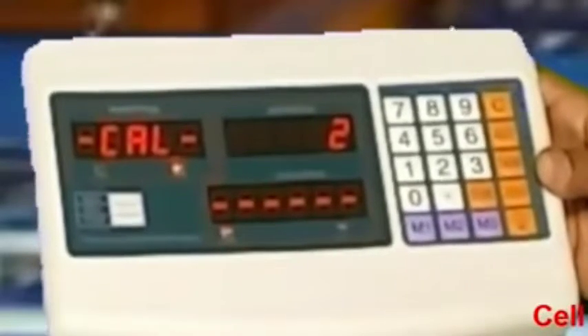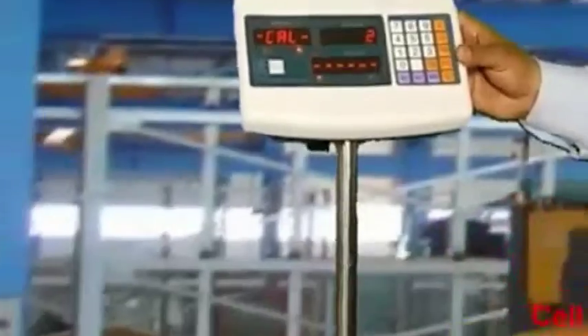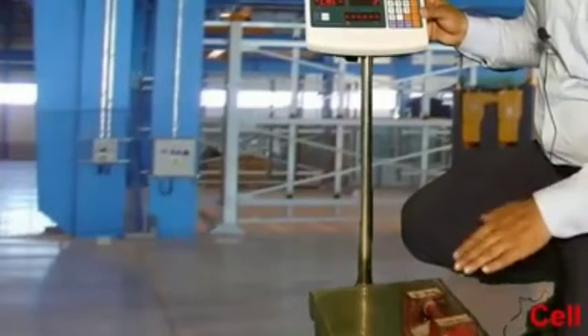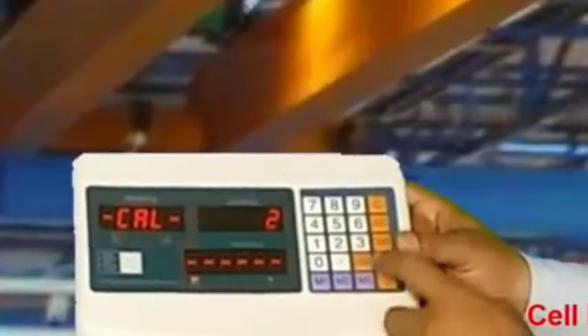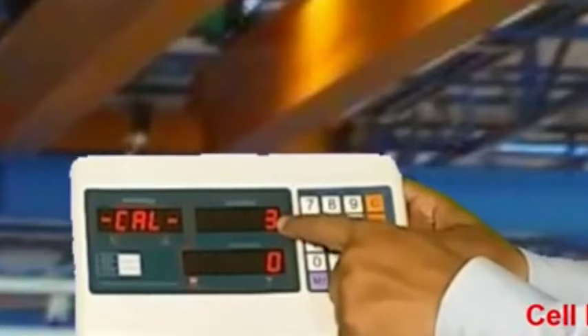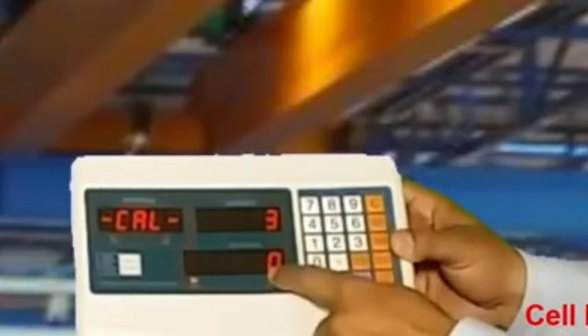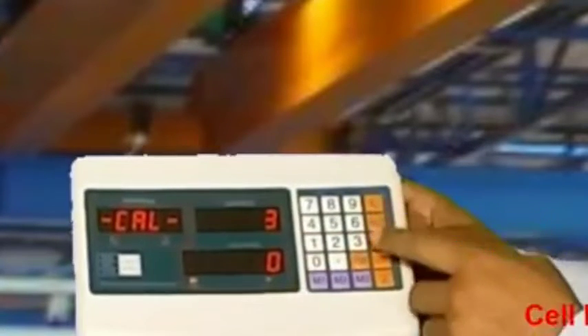When 2 comes on the screen, we put dead weight on the platform. This is 5kg dead weight. Then press tare button. It shows CAL 3 on the screen. When CAL 3 comes, we enter its full capacity.